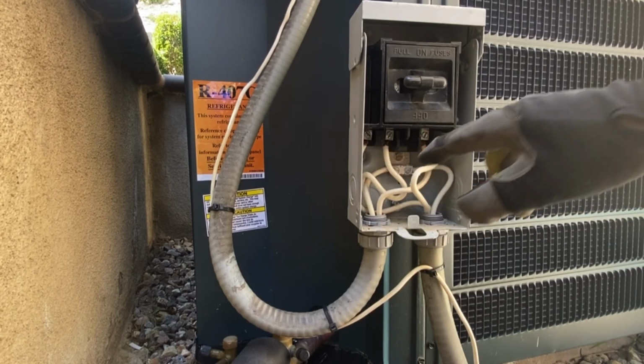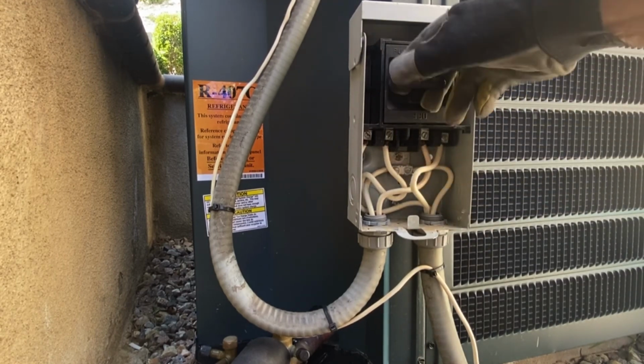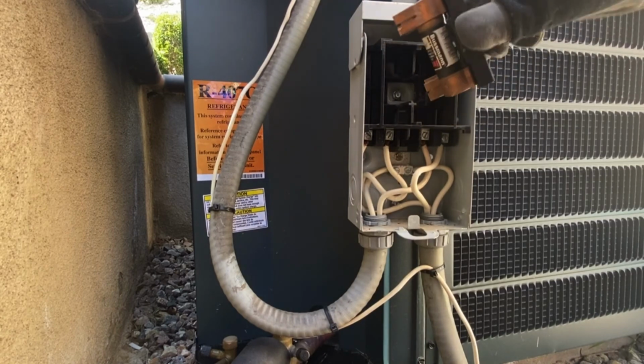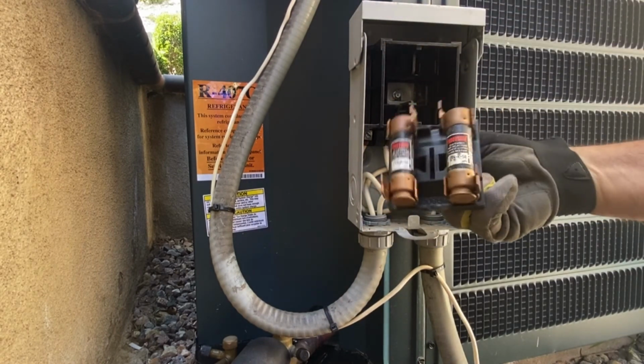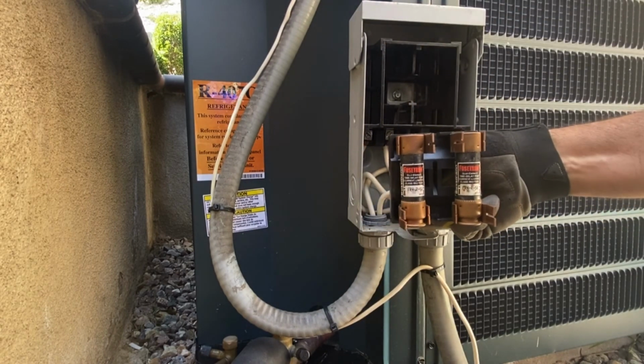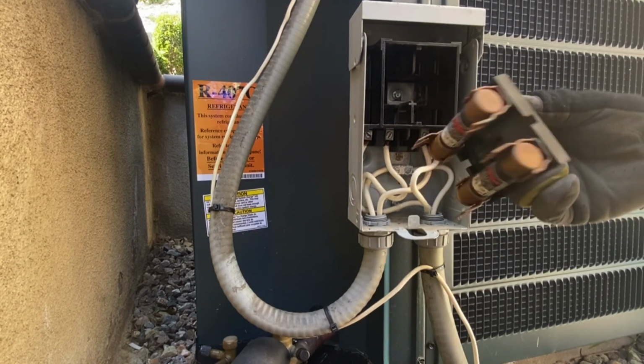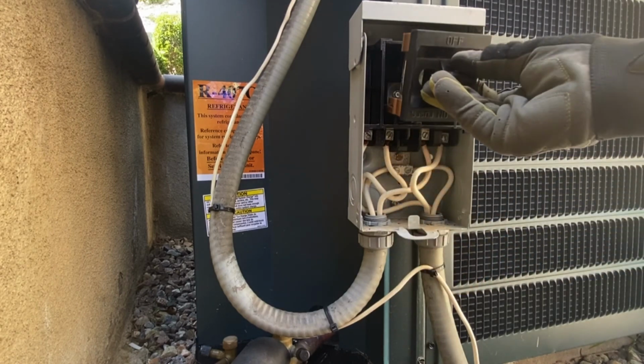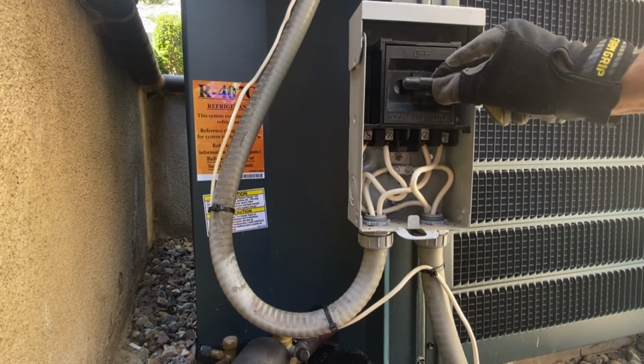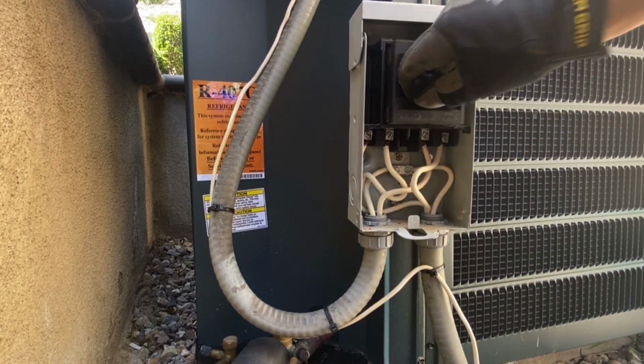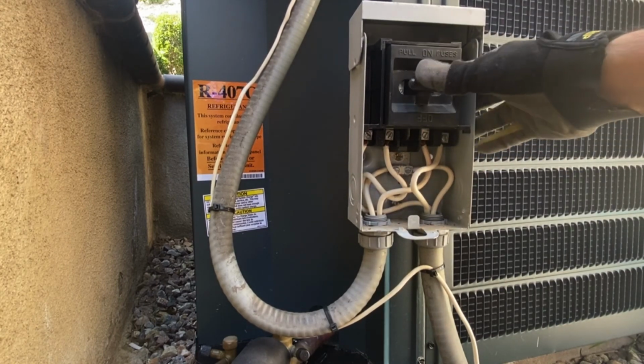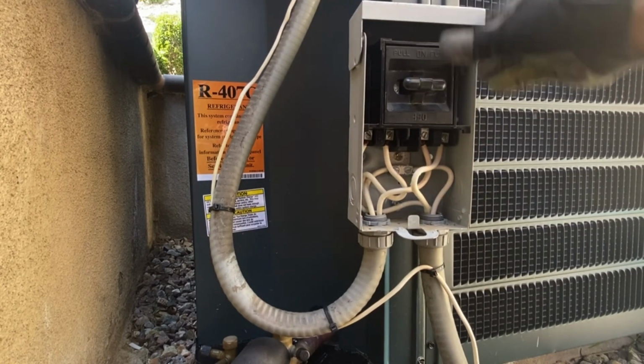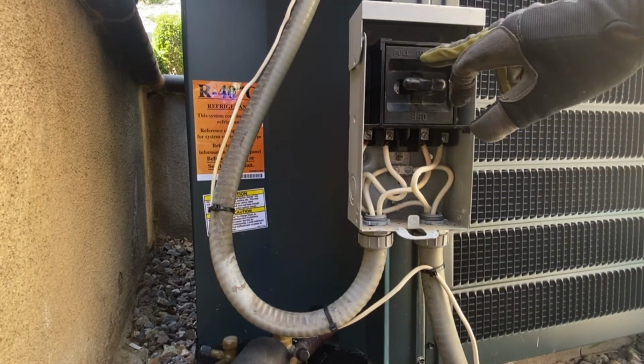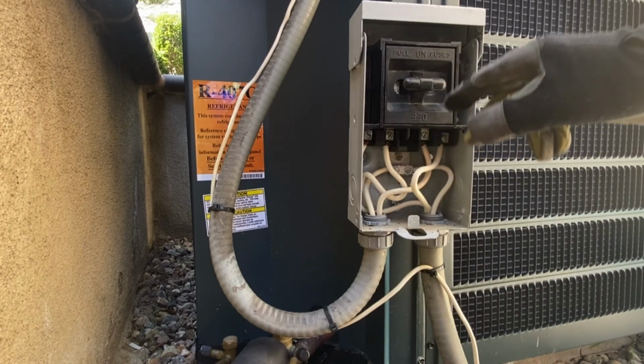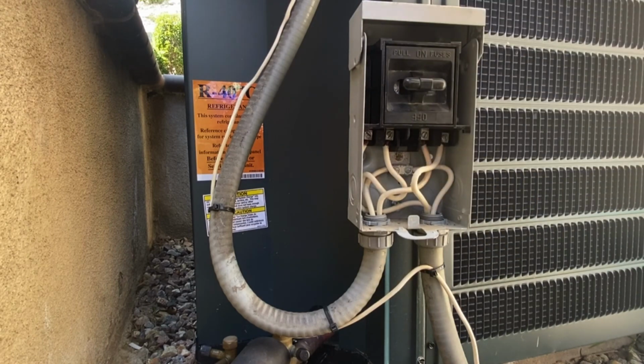Power goes into L1 and L2, goes through my fuses. You can see these are both 50 amp fuses, time delay. I'm able to put this in one direction. See, it goes in real easy. That is in the off position. Or turn it around, it takes a little bit more to push it in. I'm now in the on position, so all the power coming in goes through my fuses and through the conduit and up into my unit.